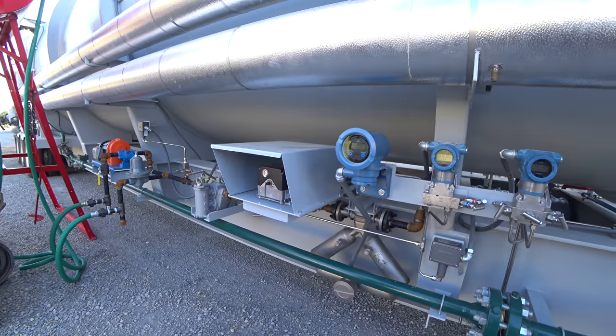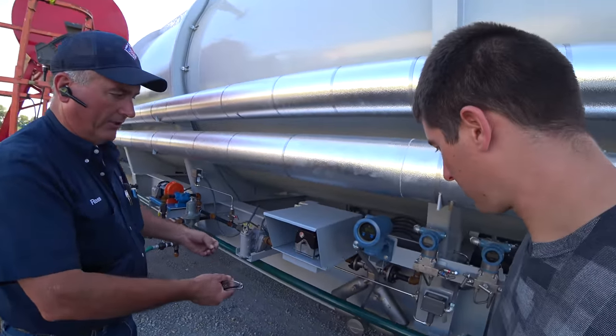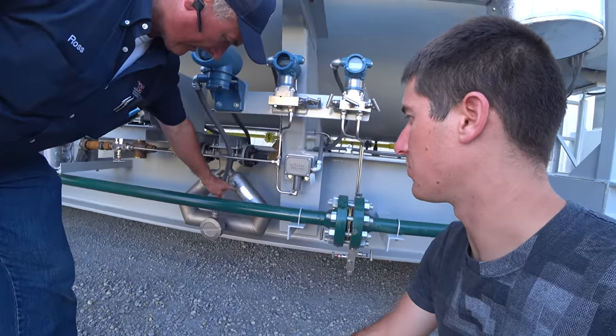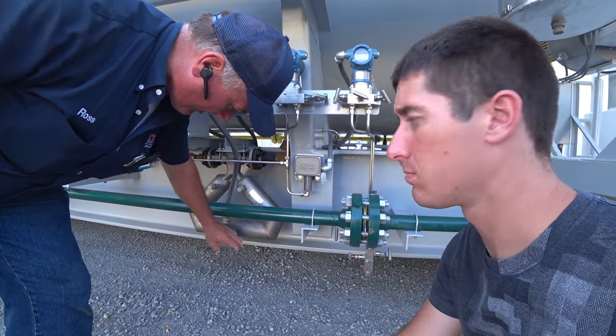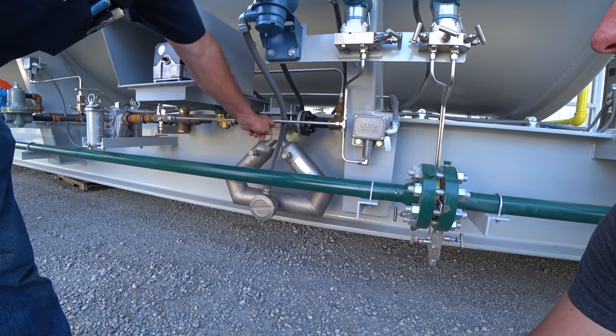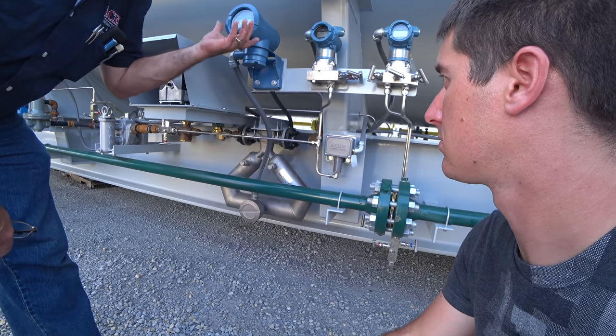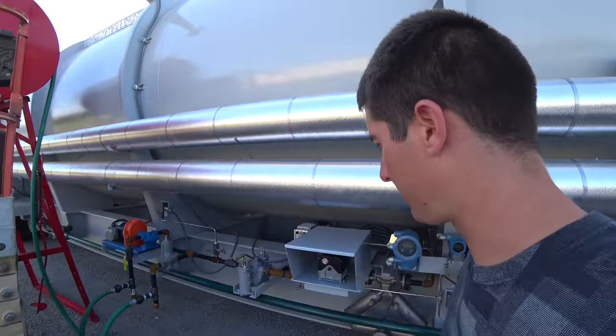Is it optical? No, it actually uses strain gauges to see how the tube deforms. There's actually a very small tube inside this tube, and it looks for deformation and it's protected by this tube. So this is just a protection. Sure. Here's where the electric sensors are wired to this tube. Yeah. And as the fluid accelerates around these corners, the more acceleration, the more the tube deforms, and the measurement is fed into this computer, which calculates the flow rate. Huh. So that's a cool way to find flow.